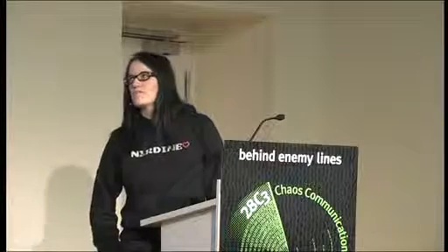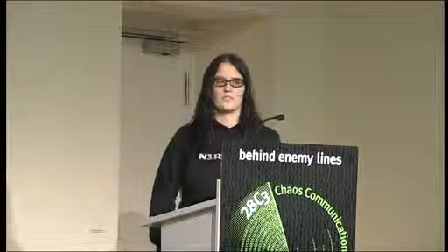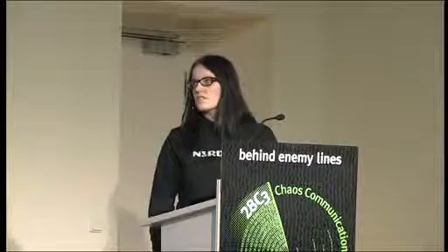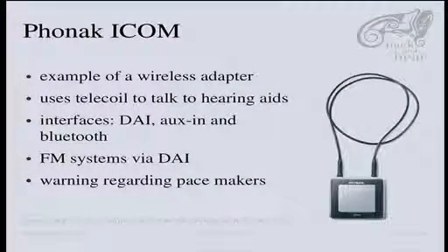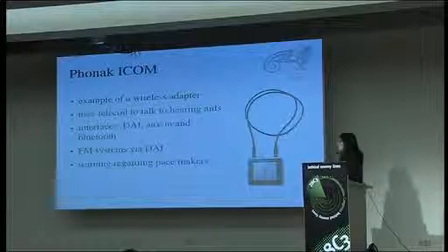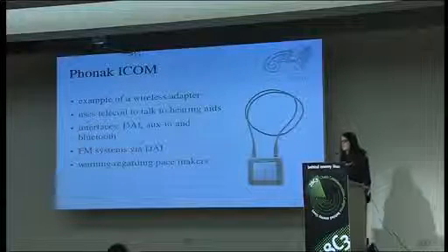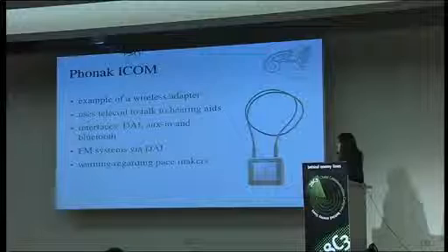Right now, you have to use a Bluetooth adapter to use your hearing aids as a headset, and there are different versions of it. This is an example from Phonak. They built a really nice thing. You hang this piece around your neck, and the ribbon is actually the induction loop that is used with the telecoil. To this gadget, you can connect several things. It has direct audio input, which you can use to plug in an FM system. It also has aux in, so you can directly plug in your MP3 player, and it has Bluetooth.